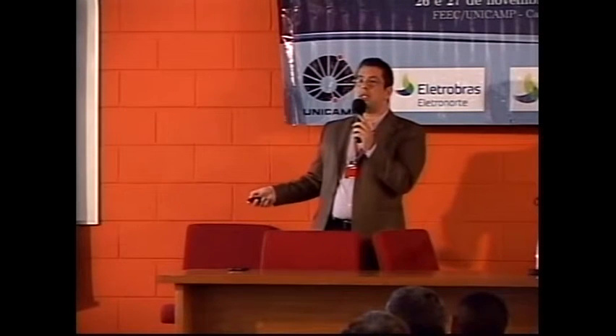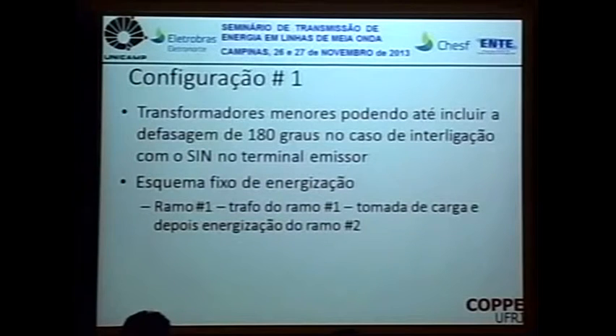This order is something that cannot be changed. Once you energize the first branch, you get the load, and then you energize the second one. The sequence of loads will always have to be very well coordinated to avoid overvoltages.